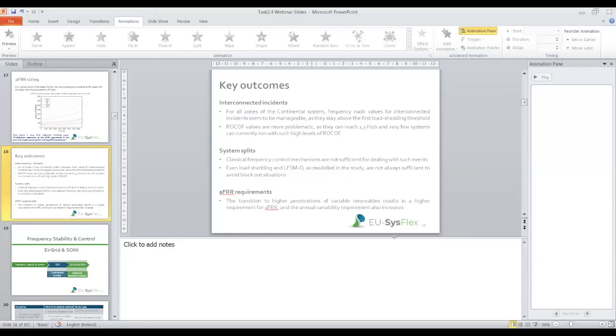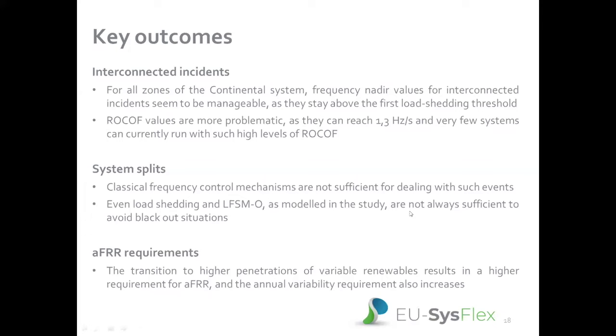So for interconnected incidents, we observed that nadir values were manageable because we observed no value below 49 Hertz, which is the first load shedding threshold. However, we had some concerns about the RoCoF values, which could, in many cases, be more than 1 Hertz per second.